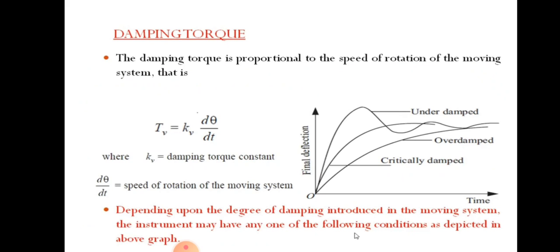First, we will see the damping torque and its graph. The damping torque is proportional to the speed of rotation of the moving system. Damping torque, denoted by Tv, equals K times dθ/dt, where Kv is the damping torque constant and dθ/dt is the speed of rotation of the moving system. So Tv is directly proportional to the speed of rotation dθ/dt. Depending upon the degree of damping introduced in the moving system, the instrument may have one of several conditions as shown in the graph.